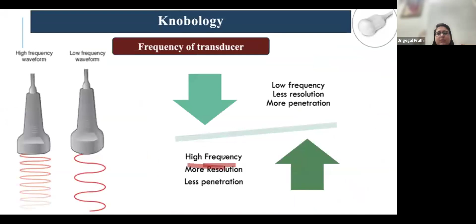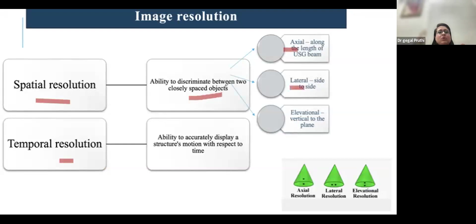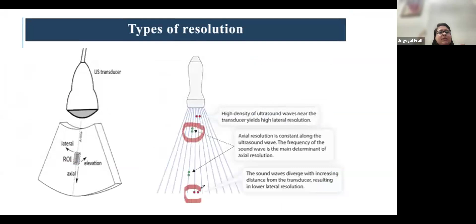Different probes or different transducers have different frequencies. So for better resolution, you need the higher frequency probes and also the larger transducer radius. So coming on to the resolution, there are two types of resolution, that is spatial resolution and the temporal resolution. Spatial resolution is the ability to discriminate between two closely spaced objects. It is either axial or lateral resolution. Axial resolution is the ability to discriminate between two closely spaced objects in the y-axis, whereas lateral resolution is the ability to discriminate between two closely spaced objects in the x-axis.